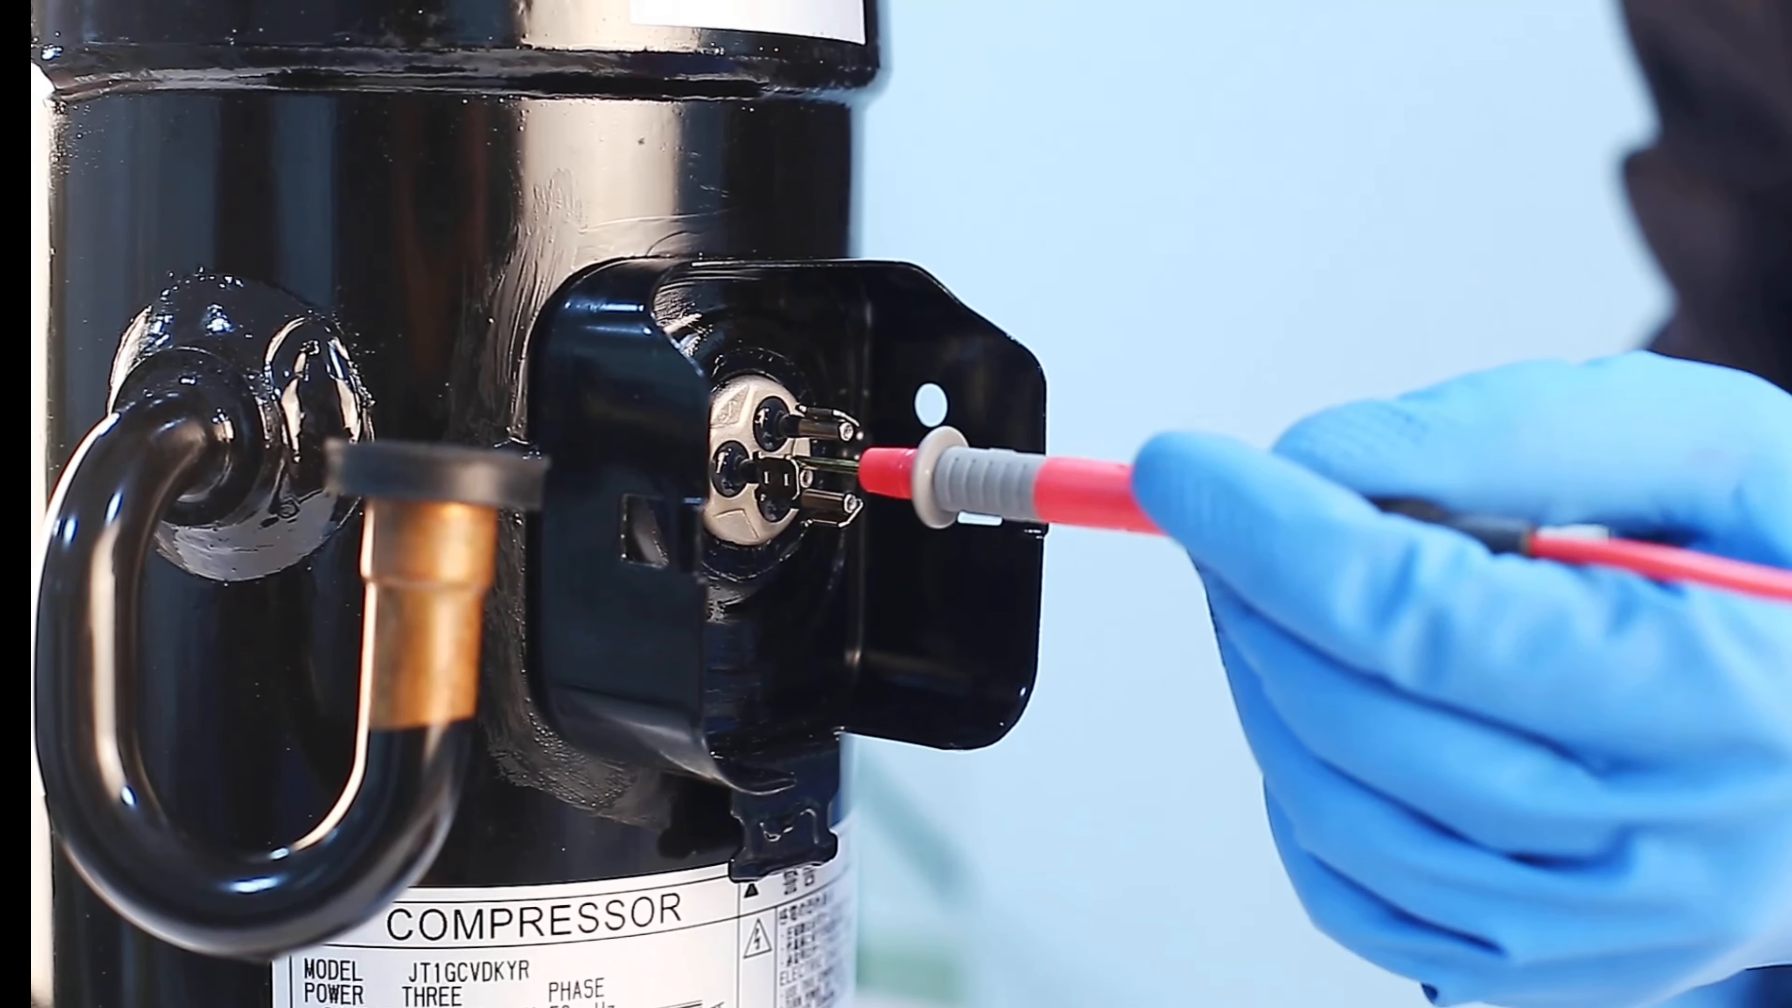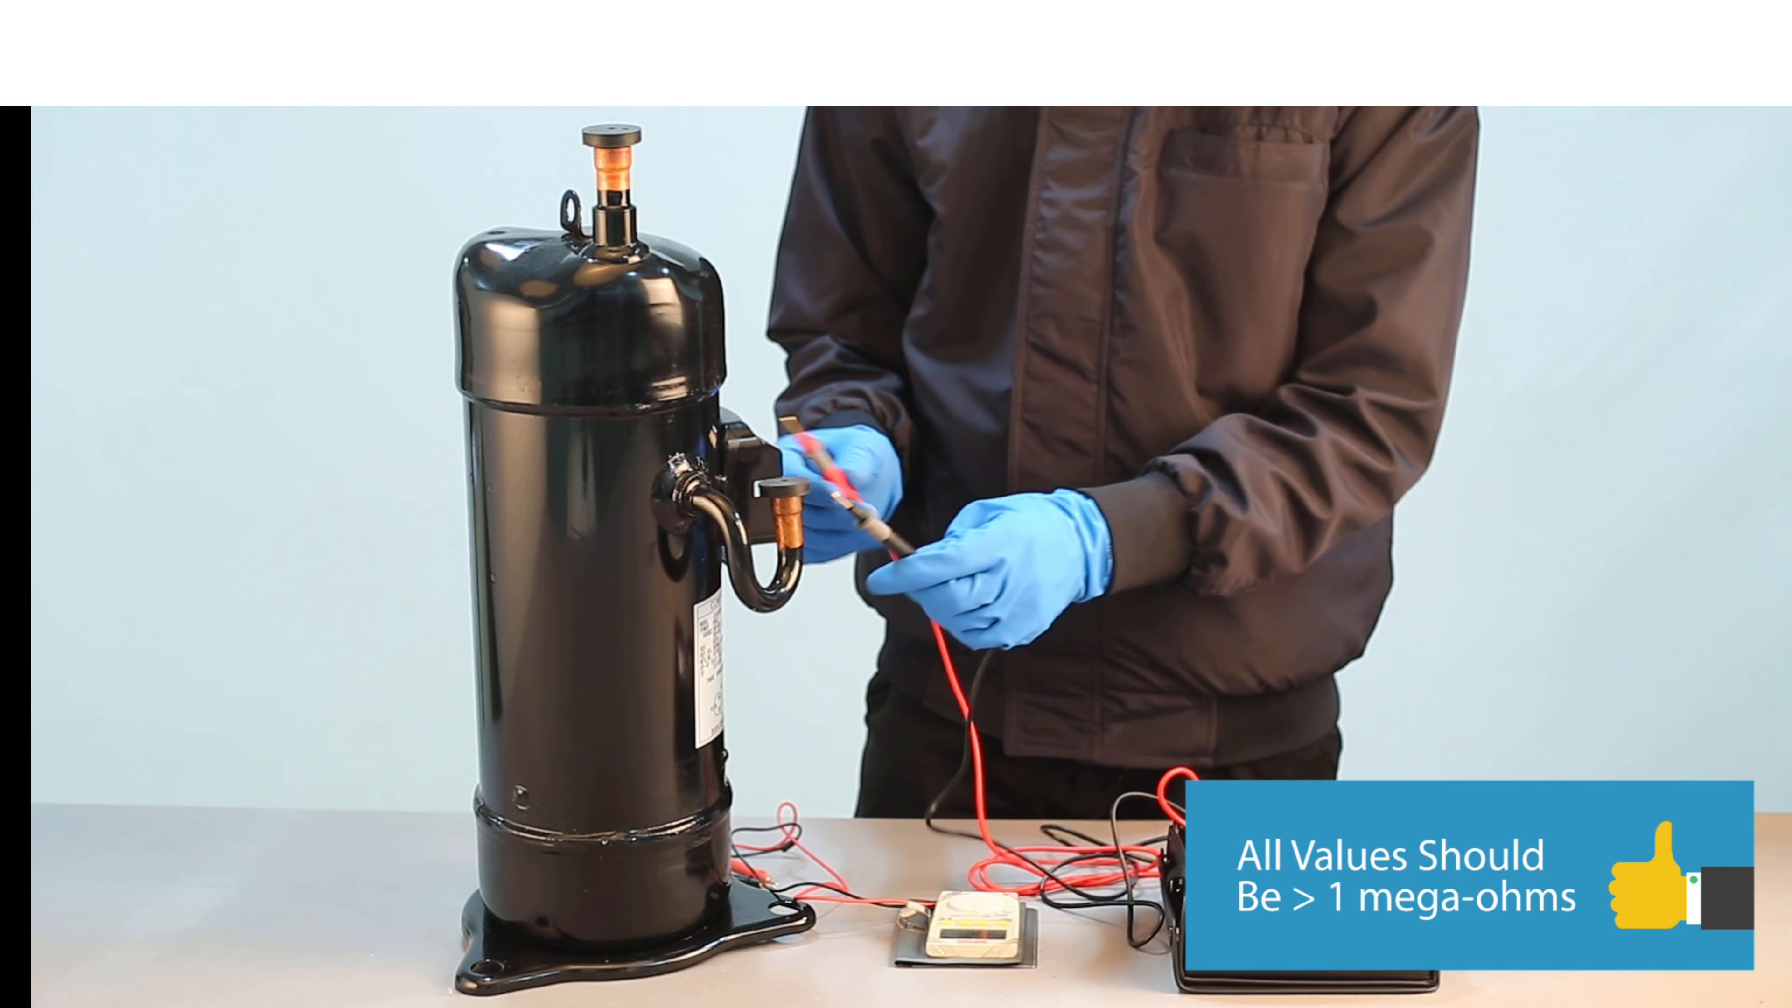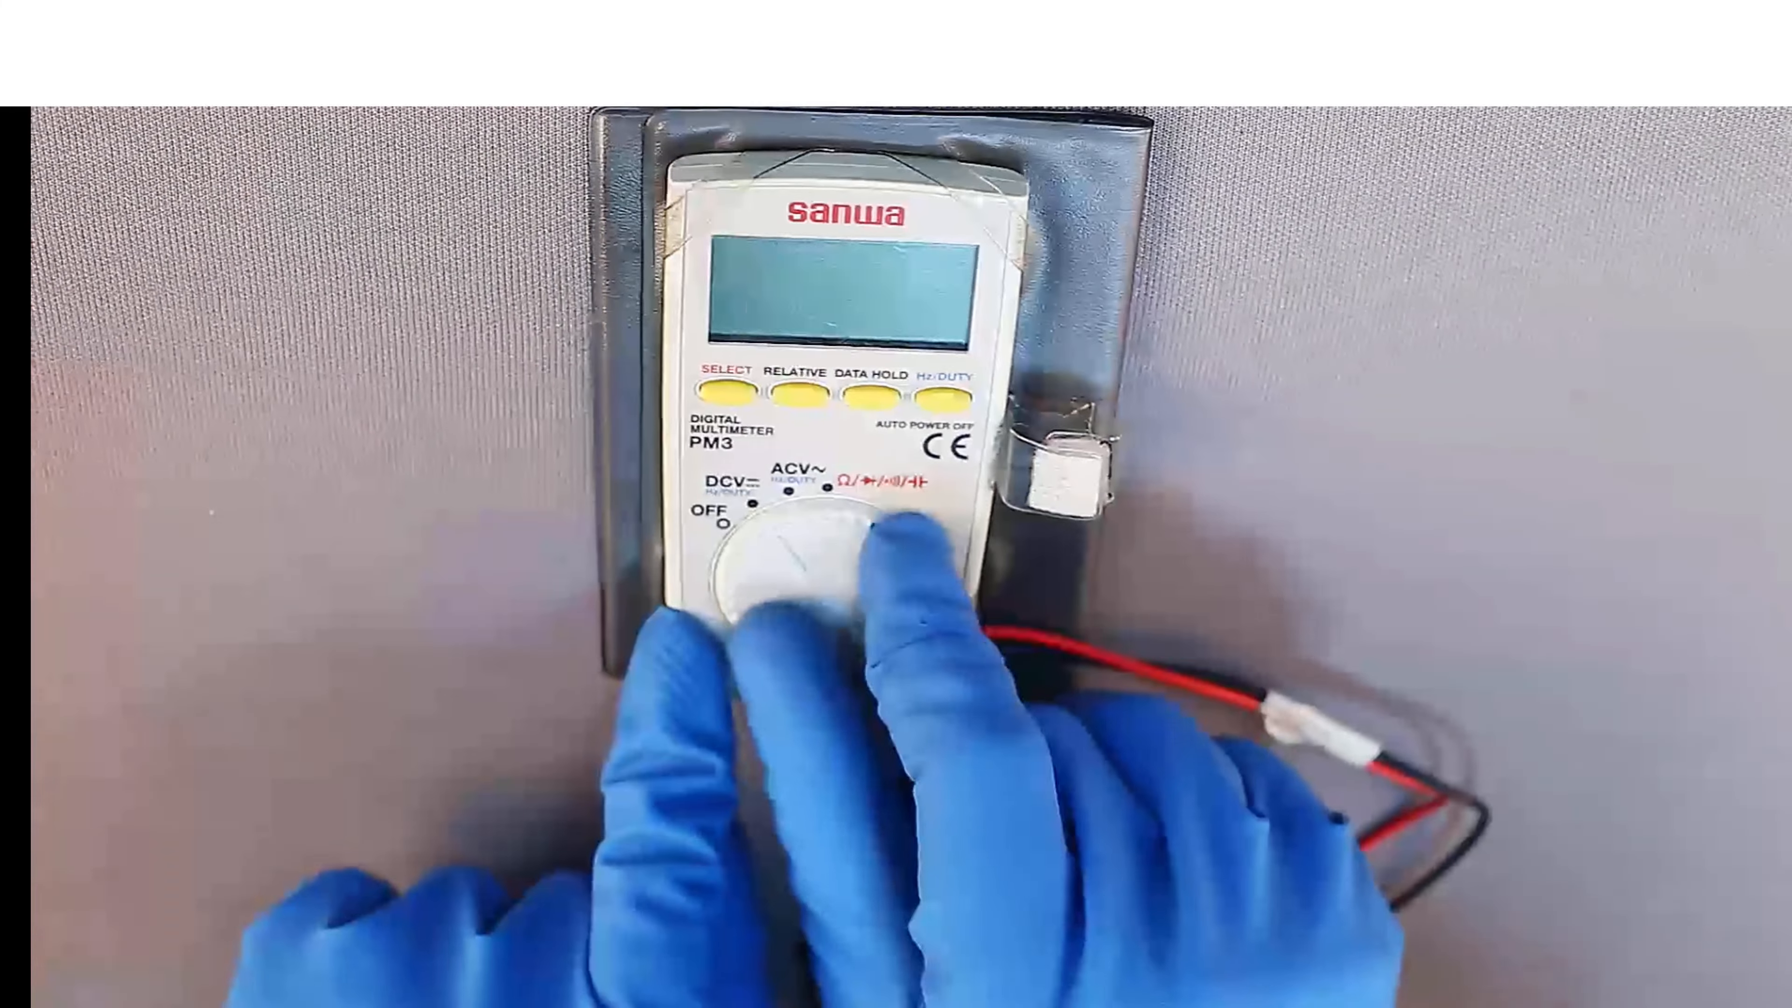Connect the red probe to U, V, and W one by one. All three values should be more than one mega ohm. If any value is less than one mega ohm, it means the compressor is defective.